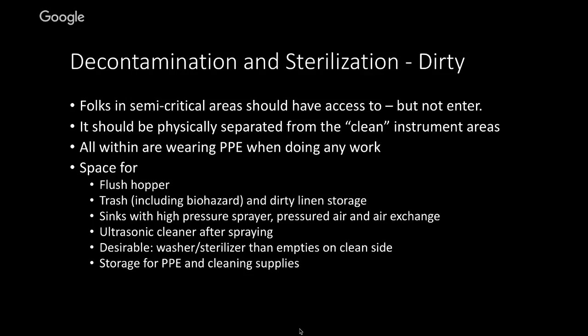And so inside the room that's going to be decontamination and sterilization, there may be another flush hopper. You're going to have trash, and of course, this is where biohazard stuff is going to go as well. There's going to be storage for dirty linen. In cleaning the instruments, a couple of things are very, very important. We've already mentioned that this be water that has either been distilled or gone through reverse osmosis, because we don't want anything with minerals in it. You should have a true professional high-pressure water sprayer and sink system there so that you can clean the instruments with more force than would come out of a kitchen sink, for example.